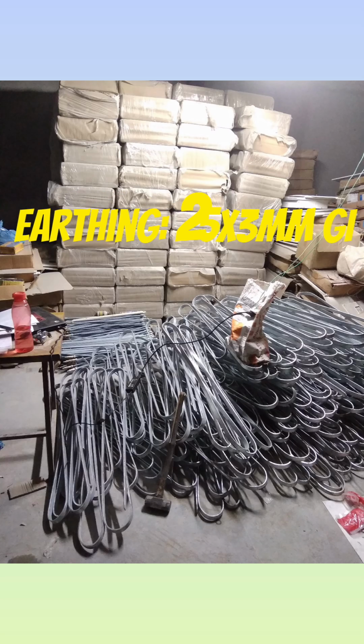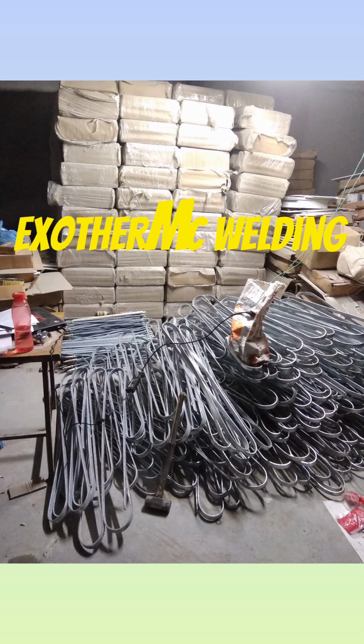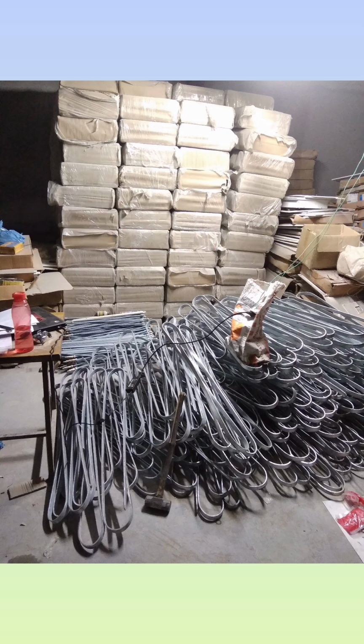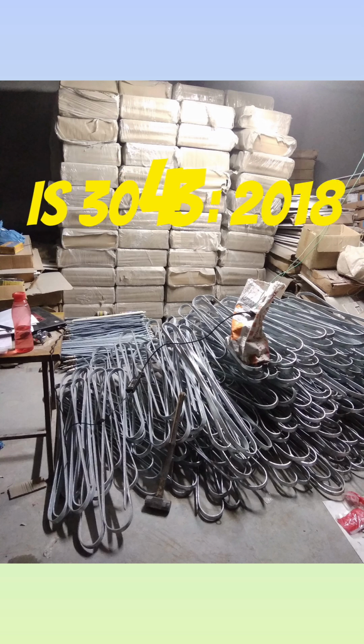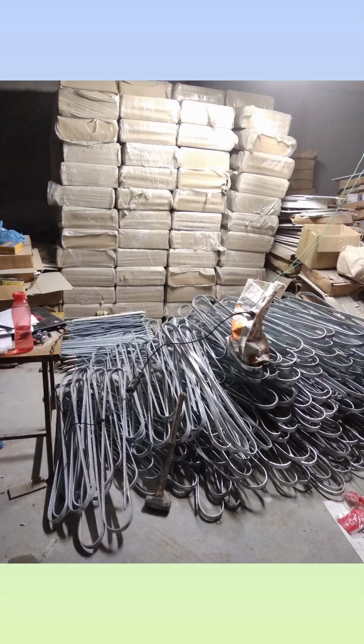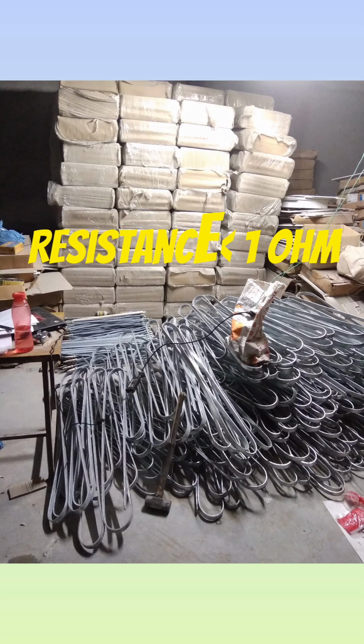Earthing system, the backbone of safety. These 25 by 3 GI strips are fabricated in the store and exothermically welded on site to form the earth grid. As per IS 3043-2018, the transformer neutral has two independent earth electrodes and the body has two separate electrodes. Combined earth resistance was measured at 0.85 ohms, which is below the 1 ohm requirement.